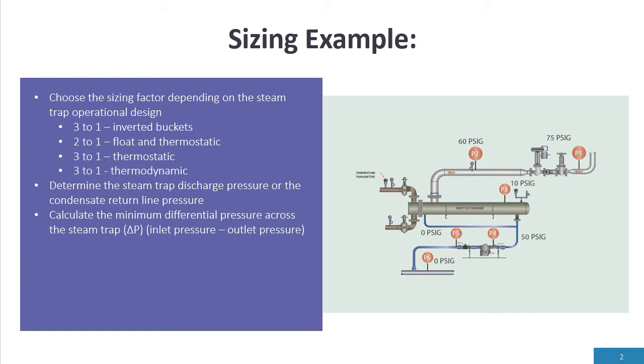Float and thermostatic is two to one sizing factor, thermostatic is three to one sizing factor, and thermodynamic is three to one sizing factor. And we talked about in part one determining the steam trap discharge pressure or condensate return line pressure.